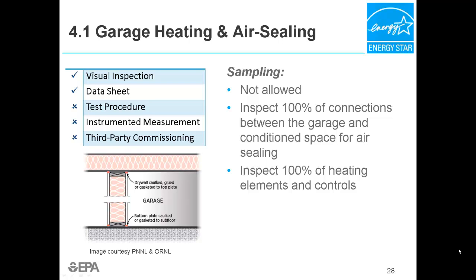During your inspection, visually confirm and use the T&V worksheet to confirm that heating systems, if present, are used only for safety considerations. These should be properly controlled and locked. Confirm that the garage is fully compartmentalized. Check for weather stripping on all doors, and that pipe and conduit penetrations have been fire stopped or sealed. This inspection will typically come at the end of construction.